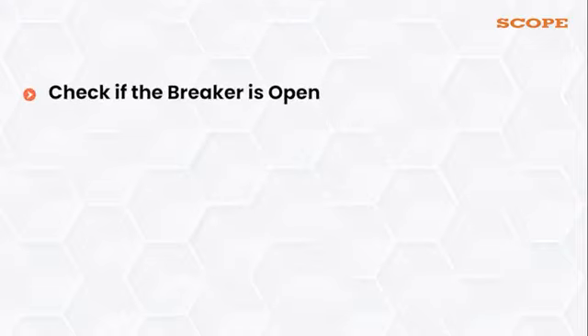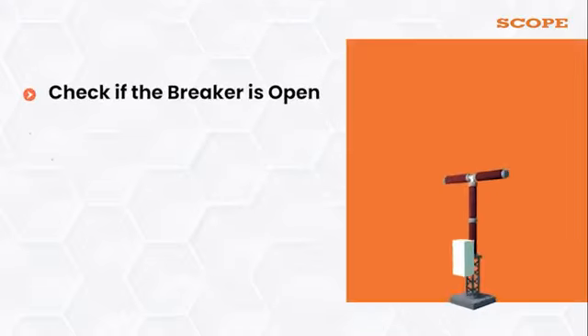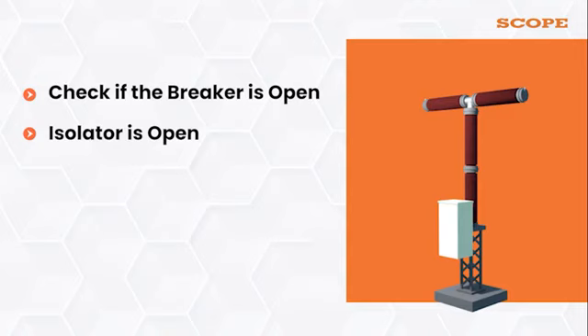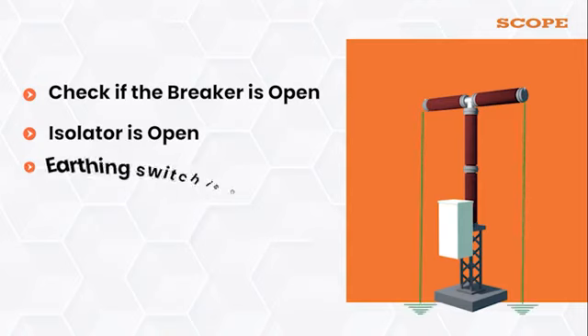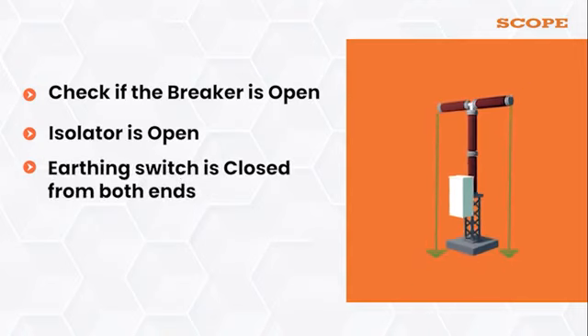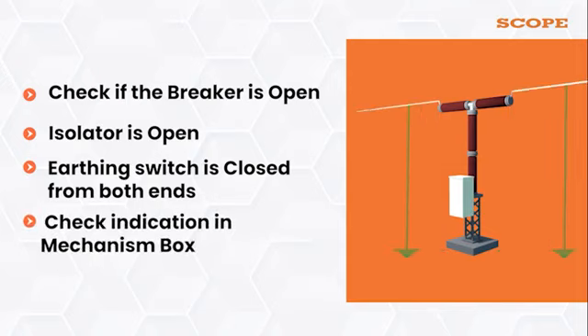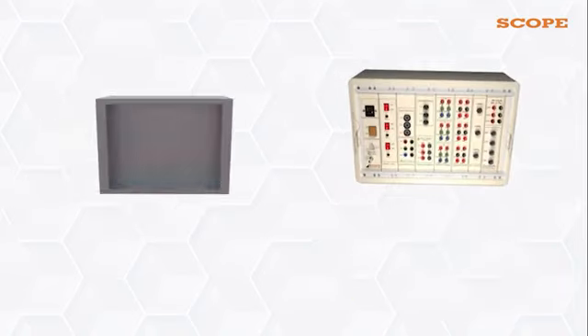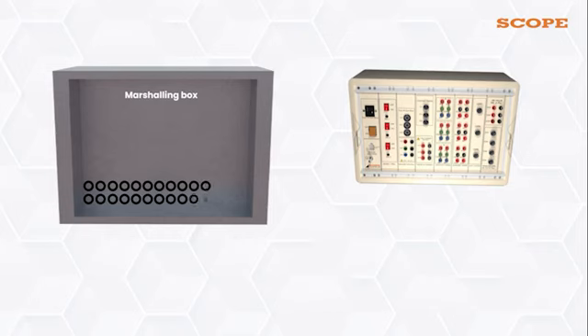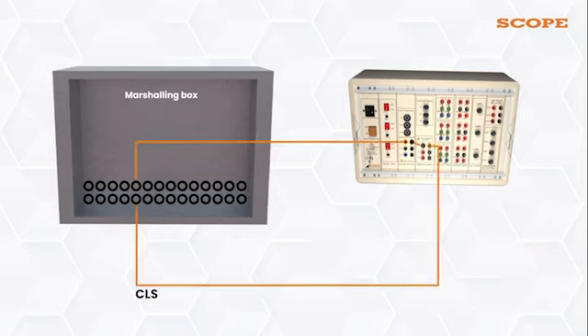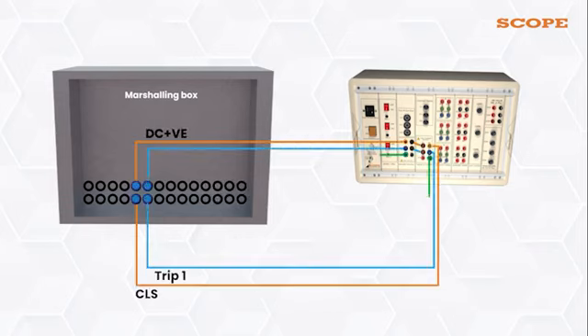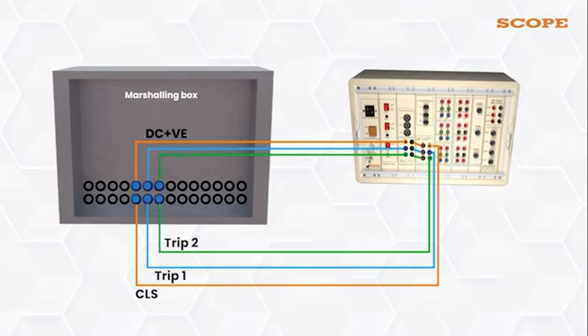Check if the breaker is open. Isolator is open. Earthing switch is closed from both ends. Check the indication in the mechanism box also to be double sure about the same. Once you have tested and confirmed this, let's take control of the breaker from Module 3 to close coil, trip 1 and trip 2. Let's continue to connect the coil current at the mechanism box.